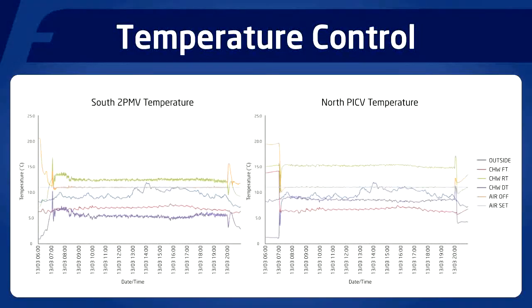After 2 weeks, we picked up the pressure independent control valve and moved it from the south air handling unit into the north air handling unit, and took the conventional valve from the north and installed it on the south air handling unit, and once again recorded the temperature performance. We can note from these two graphs that the delta T of the water is much higher on the air handling unit installed with the pressure independent control valve than it is on the air handling unit installed with the conventional control valve. We can also note that whilst both set point temperatures are maintained fairly well, there are less oscillations, and the amplitude of the oscillations are less on the north air handling unit, which has the pressure independent control valve installed on it.